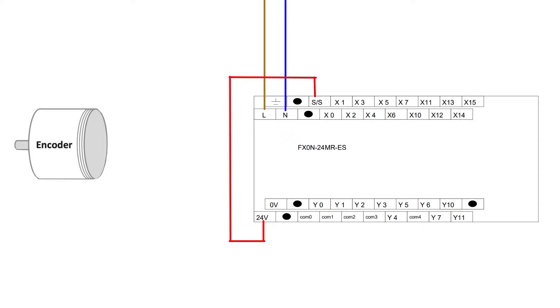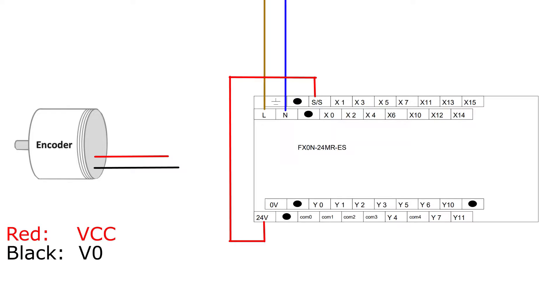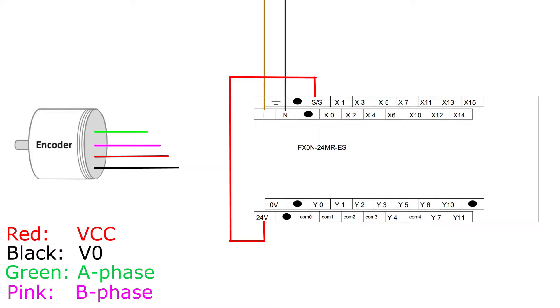From the encoder I am using there are four wires. Two wires for the 24 and zero voltage DC. Then two wires for the A and B phase. From the red and black cable I want to connect to the PLC's 24 and zero voltage DC output terminal which will give power to the encoder.